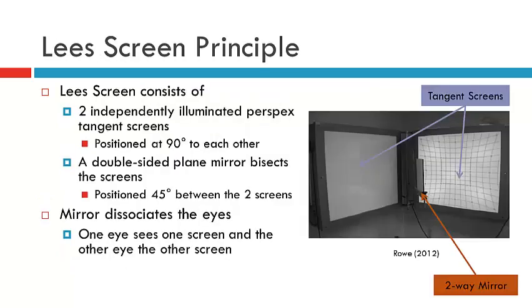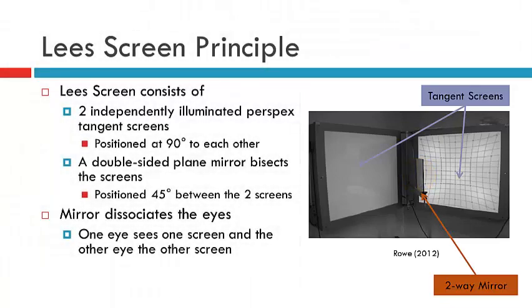The Lees Screen consists of two independently illuminated perspex tangent screens. We can see here in the image on the right that this is the tangent screen that's not illuminated and at 90 degrees here is the illuminated tangent screen. We also have a mirror that bisects the screen at 45 degrees. The mirror in dissociating the eyes will effectively result in one eye seeing one screen and the other eye seeing the other screen.